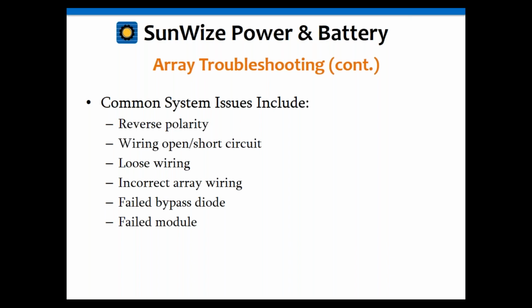A failed bypass diode. And again, we'll have a new tech note on that coming up, and I think I addressed that in more detail in the troubleshooting webinar. And of course, a failed module. If you've got an older one, that can happen, or if you've got one that's been damaged in some way, from the backskin or something like that, then it can fail for those reasons.